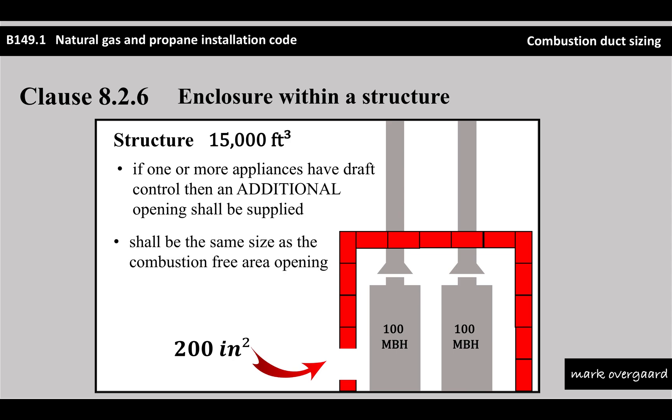So we get that flue gas spillage - that's a problem. What we need is that additional opening, and it's the same size as the combustion-free area opening down below: 200 square inches. What that will do is create a nice convection current within that whole system and take those products of combustion out. And because the structure is leaky, it will take those out of the whole structure as well.